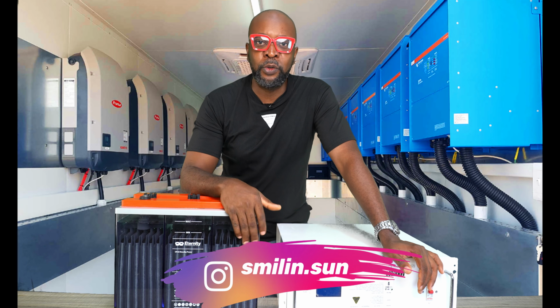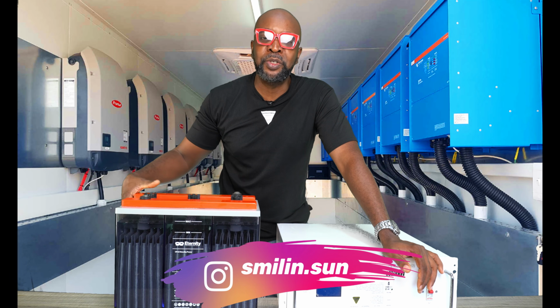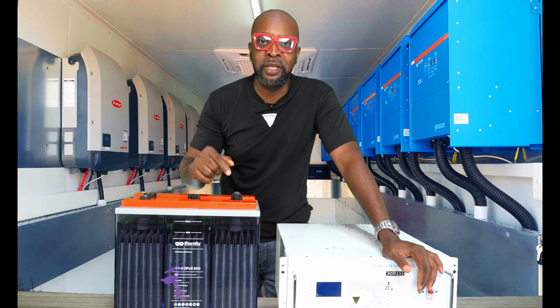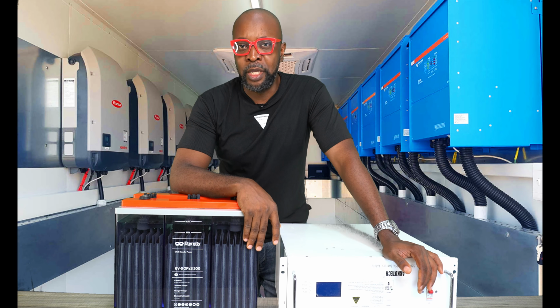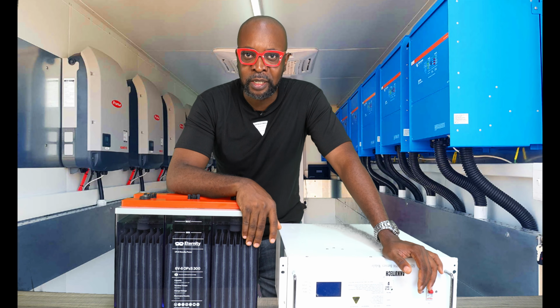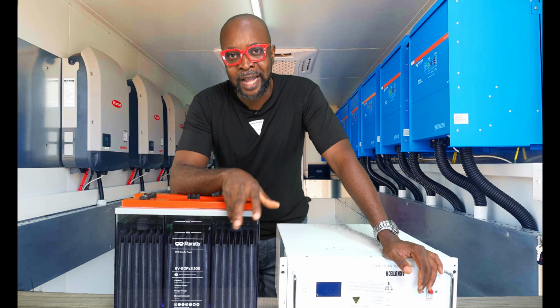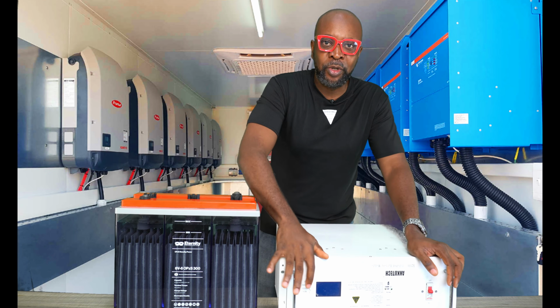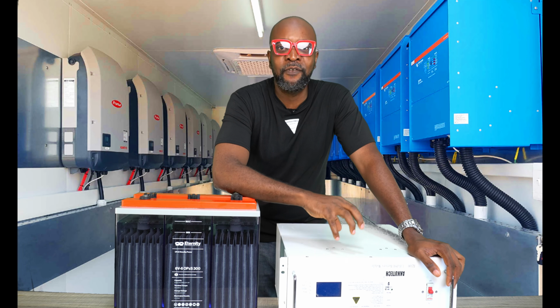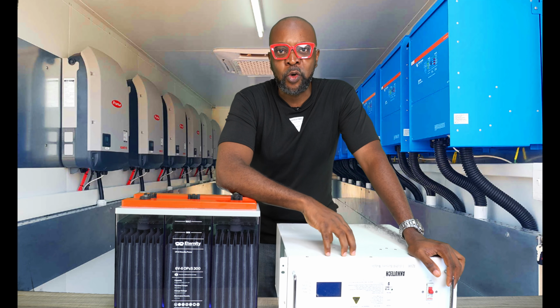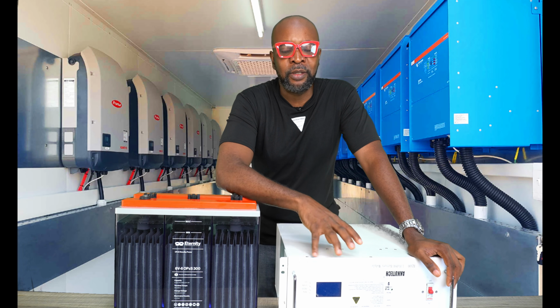That's what's available for you to use. You can't drain more than 50% out of these batteries. Once you begin to drain the batteries beyond the threshold, which is 50%, you are putting the cells of the battery in danger. But for the lithium battery, it's a lot more extended. You can drain 95% of the energy stored in this battery without putting the cells in danger.